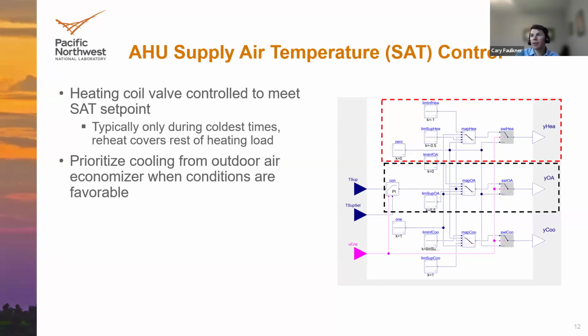And then the next aspect of this control is going to be the outdoor air economizer cooling. So I should mention that this system includes an economizer for outdoor air, which allows the potential of free cooling when conditions are favorable, particularly when it's cool outside, but you still need cooling in the building, especially with people and equipment generating heat. So that's going to prioritize cooling the zones using outdoor air.